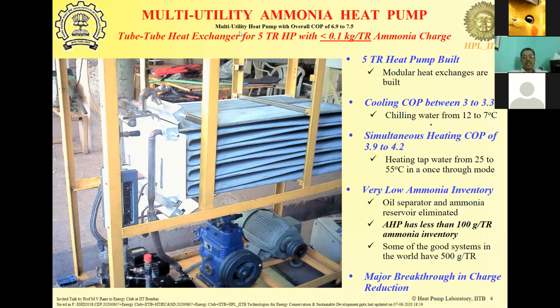Now, in this particular case, the charge for the refrigerant could be reduced to as low as 0.1 kg per ton. Just to put things in perspective, a conventional air conditioner would have somewhere around 0.6 to 1 kg of refrigerant per ton of air conditioning. And in this case, because of the tube configuration, because of low internal volumes of the heat exchanger on the refrigerant side and higher heat and mass transfer coefficient, we were able to reduce the mass of refrigerant required to this. Some of the new refrigerants, like flammable refrigerants such as propane, this technology will be very helpful for that also. And of course, the reliability of this heat exchanger is very good because of the double wall construction.